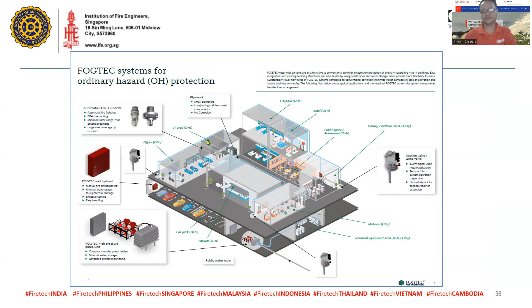In industrial risk protection, FOGTEC is also very much applicable because in a certain plant, you can use this FOGTEC wall hydrant, and you can use this stainless pipework as well. And these nozzles are the same application. And there is a section valve. The use of a section valve is, if you have a lot of zones that you're going to protect, then there's a section valve that can be used. And one more thing, there is a FOGTEC cylinder unit. This means there is a cylinder for nitrogen and water. It's a compact standalone unit, low refilling cost, ideal for object and small enclosure protection.